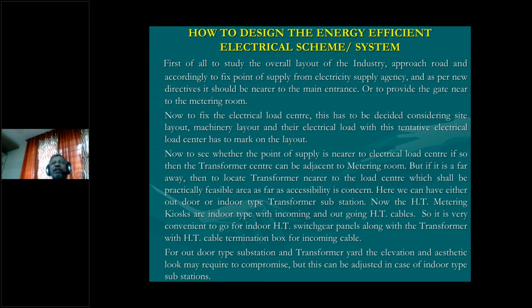So if you consider the I square R at 11 kV, 22 or 33 kV, that is the HV side, and on the LV side the losses are very high. So if you place your transformer away from the load center, your LT distribution network will be extended. The length will be more, so you will be flowing more current through your LT cables, and you will face tremendous losses.